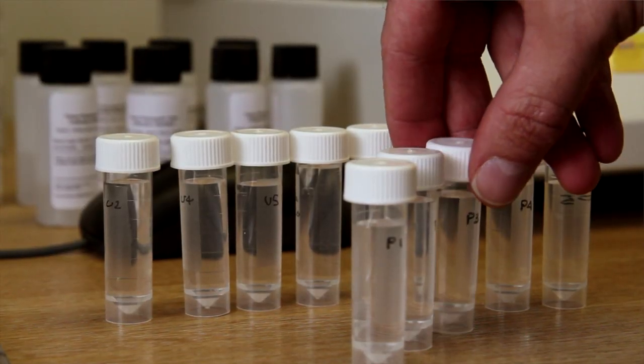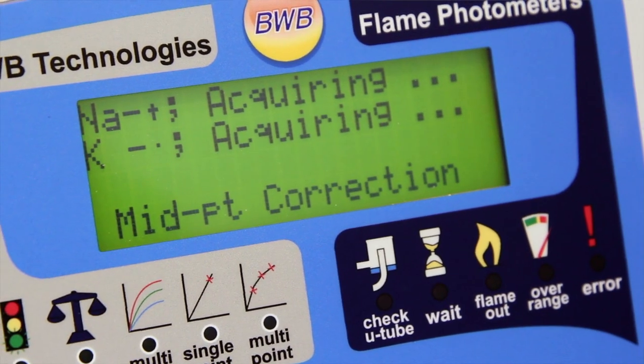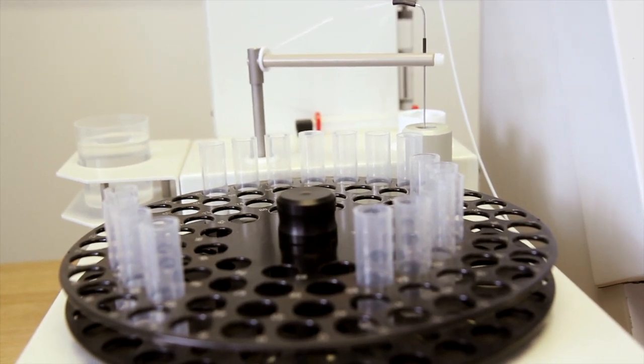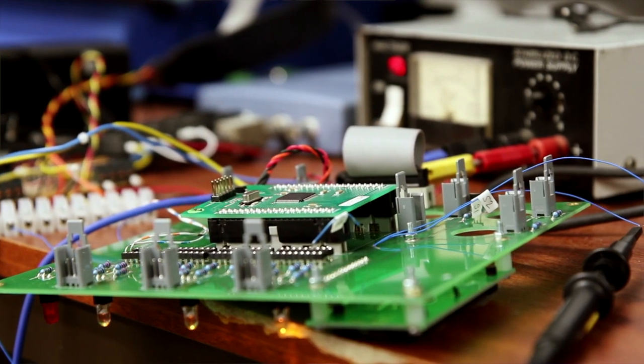The basic difference between the bio and the XP is there are built-in curves, which are separate curves for serum testing and urine testing. The user can then, on a daily basis, correct those curves and use the machine straight away. I've now automated the calibration process so that the end user can quite easily recalibrate the machine with the auto-sampler. The whole team is constantly trying to think of ways of improving it — we're always adding new ideas and new designs, sitting down to discuss them as a team, doing a lot of research, and trying to find the best way forward for the XP unit.